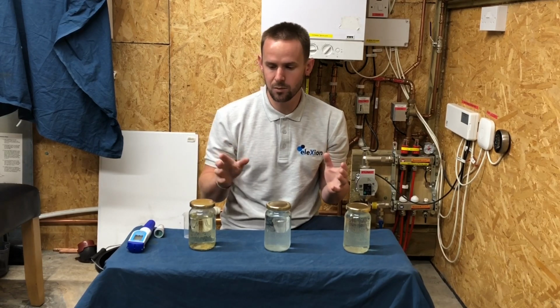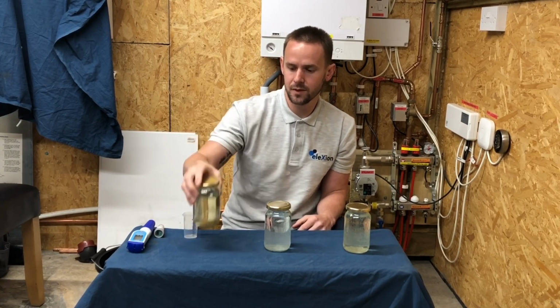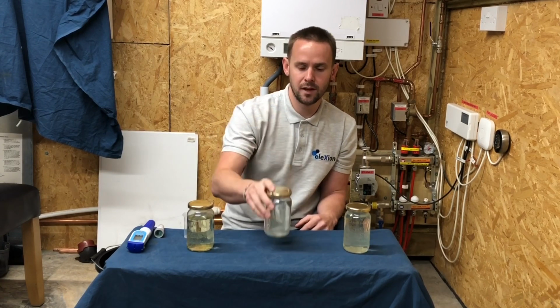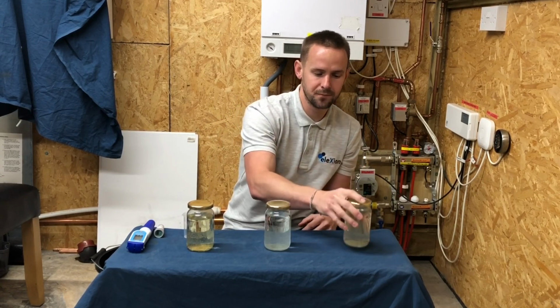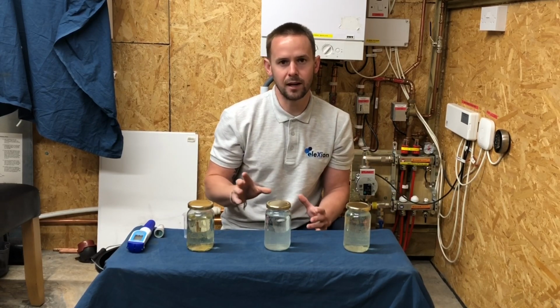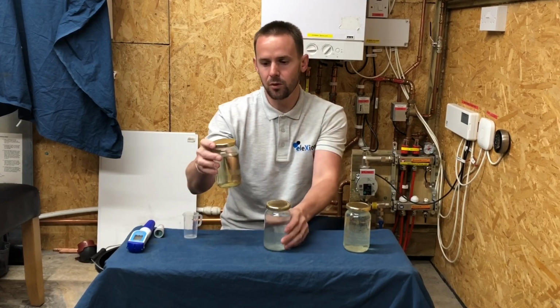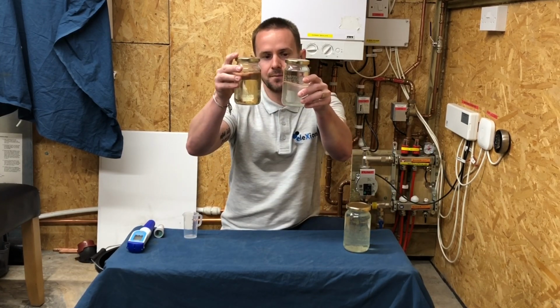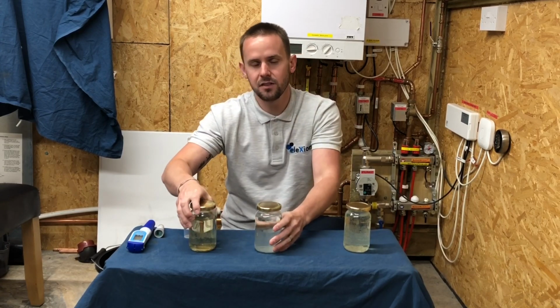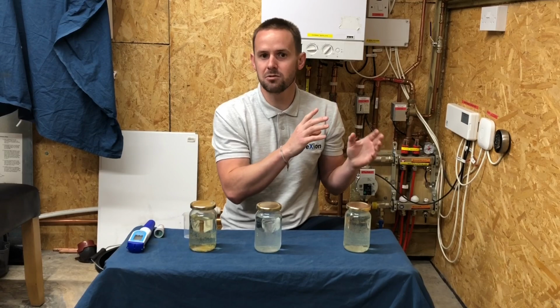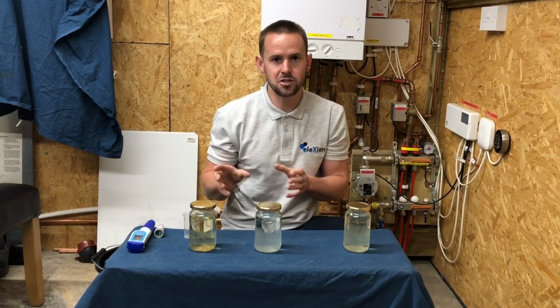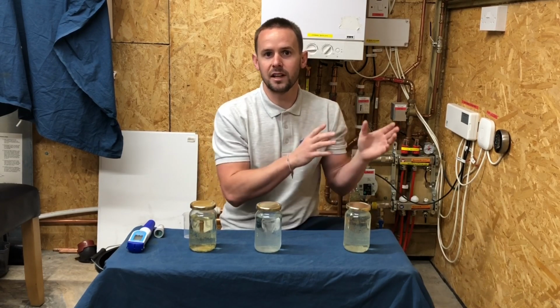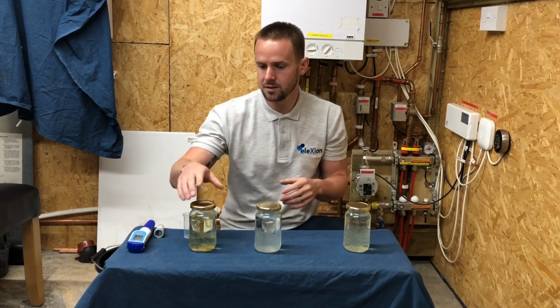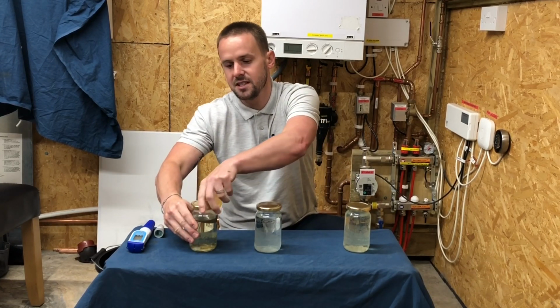We've got our 3 samples here. This was the system water. This is pure Clarimax water. And this is now our new system water. It's going to be quite interesting to see what the existing system water was like, because when it came out it looked pretty clear, but when you hold the two up there is a slight yellow tinge to it. Speaking to Alan, he did a video recently and he had some X800 running through these radiators, so this could be residue left from there. It's going to be very interesting to see the difference in conductivity, having the cleaner in there compared to the normal tap water. So we're going to do the existing system water first.